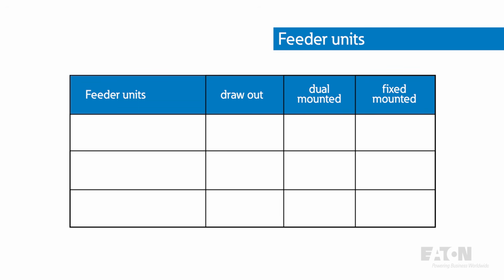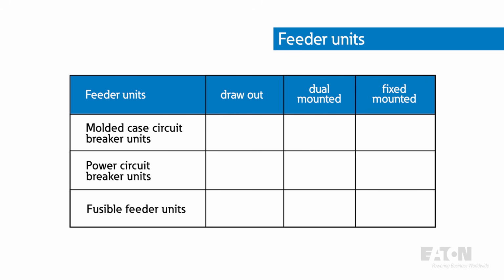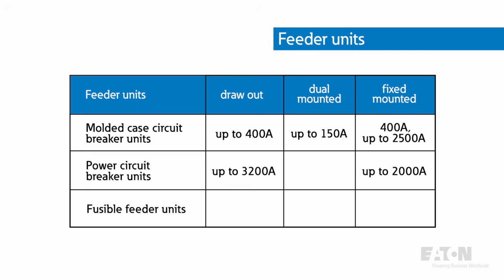Feeder units are available with either molded case circuit breakers, power circuit breakers, or fusible switches that feed a variety of different loads with different power levels. Molded case circuit breaker units are available as draw-out up to 400 amps, with dual mounting available up to 150 amps. Units above 400 amps and up to 2500 amps are fixed mounted. Power circuit breaker units are available as either fixed mounted up to 2000 amps or a draw-out up to 3200 amps. Fusible feeder units use a visible blade disconnect switch and are mounted in draw-out units through 400 amps with 30 and 60 amp ratings available in dual mountings. Fixed mounted switch ratings of 600 and 800 amps are also available.